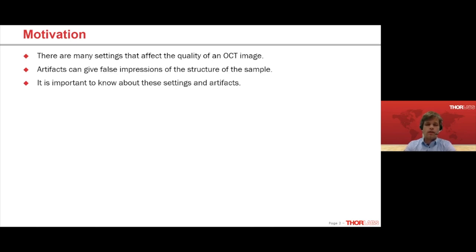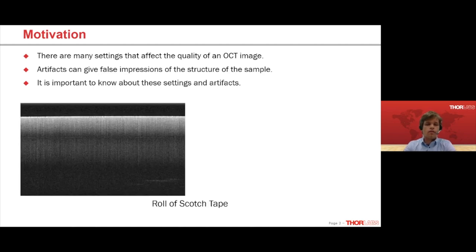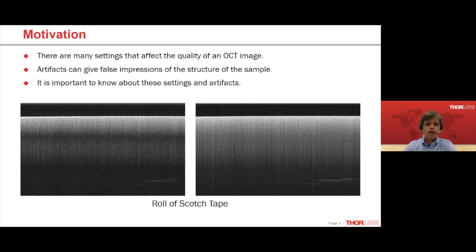I'll show you two examples of the same sample — a roll of scotch tape. On the left side you can see an OCT image where it's really hard to distinguish the individual layers stacked on top of each other, and there's a dark band in the middle. By changing the settings of this OCT system, I get the image on the right side: no dark band, and you can clearly see the individual layers. Just changing the settings can improve OCT image quality dramatically. It's easy to get an OCT image, but much harder to get a good one.